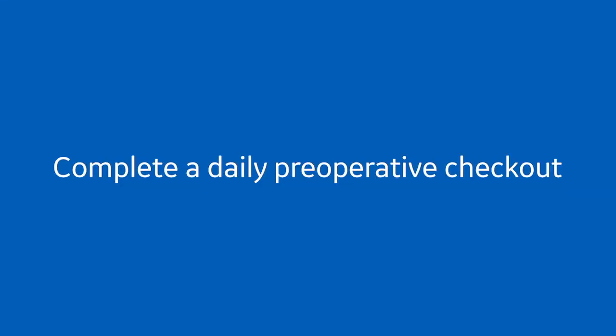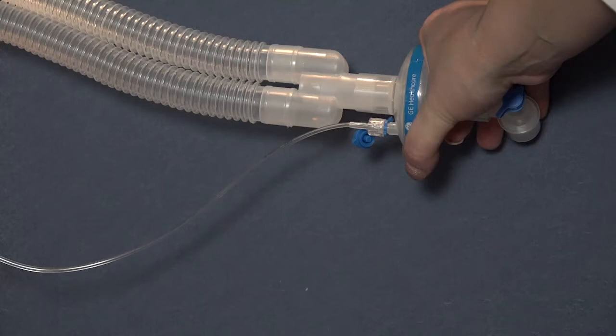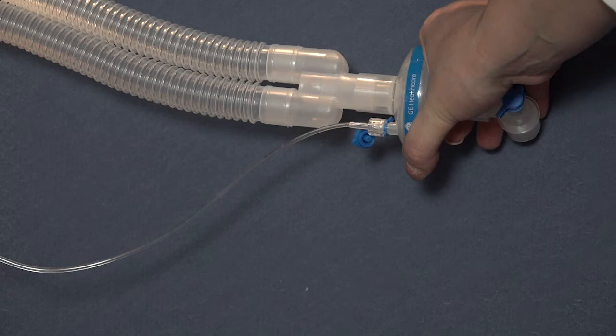The power should be cycled once every 24 hours. Complete a preoperative checkout as described in the user's manual. The anesthesia machine is intended to be power cycled and fully tested once a day. All accessories that will be used during the case should be attached to the circuit to ensure accurate circuit compliance.